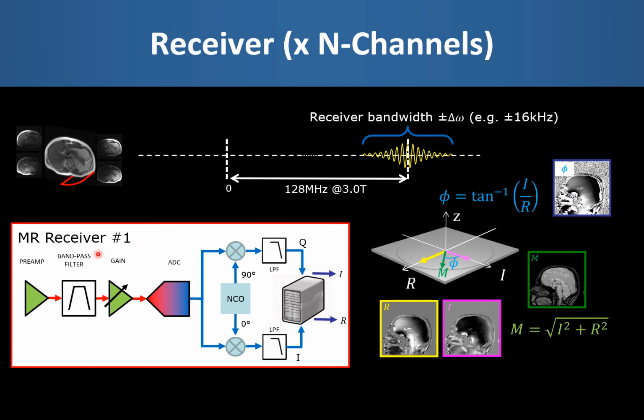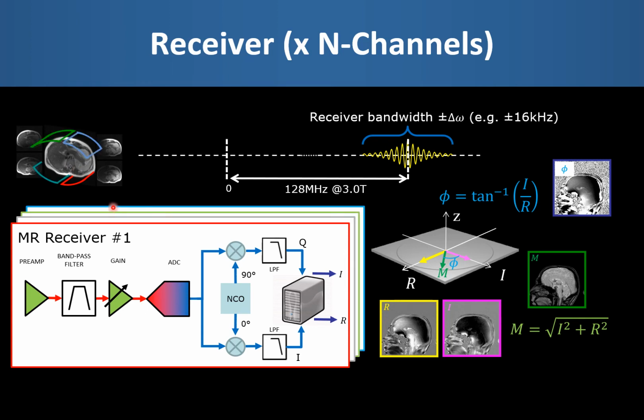This is a typical architecture of a modern MRI receiver channel, and as we have said, we have one of these receiver channels for every element that makes up our coil array. So in this case we have 4 coil elements and therefore 4 receivers. Each receiver takes the analog voltage from the coil following some low noise preamplification, bandpass filtering and some variable gain measurements. The analog signal is then digitized.